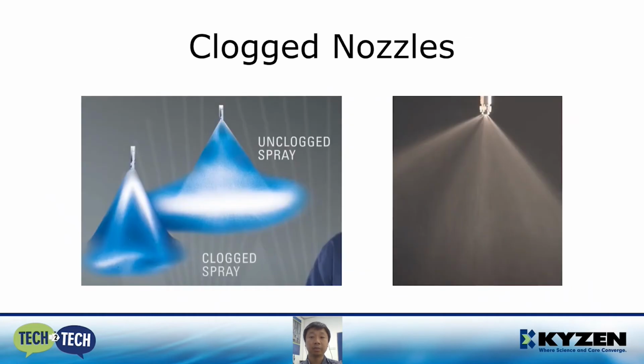Upon observing spray pressure increase, it should be associated with clogging of the nozzle. This picture shows a typical spray pattern with a clogging situation. The spraying coverage area is drastically reduced, which may compromise the cleaning outcome. The picture on the right obviously shows liquid spraying out at angles on both sides that are not the same. Running at high pressure could damage sensitive components, but a clogged nozzle can be cleaned with careful handwork.